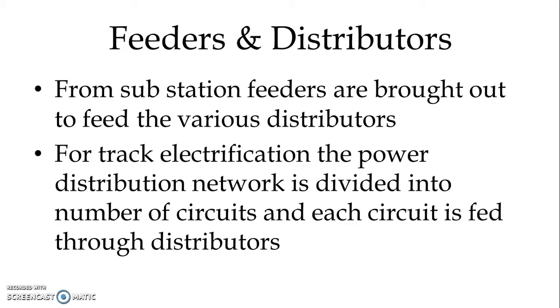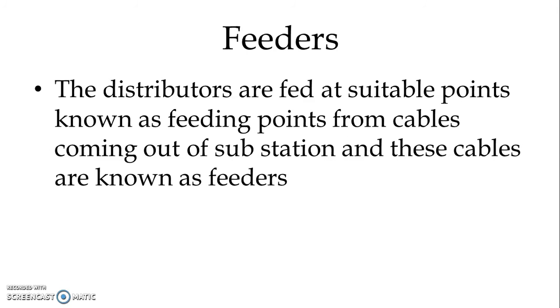For track electrification, the power distribution network is divided into a number of circuits and each circuit is fed through distributors. The cable or overhead line coming out from the substation to supply power at certain fixed points is known as a feeding post. We have several feeding posts, and we take overhead lines or cables from the substation up to the feeding post to supply power for the distributors. The distributors are fed at suitable points known as feeding points from cables coming out of the substation, and these cables are known as feeders.